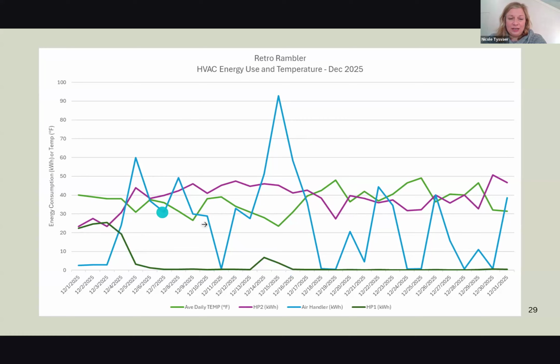And while the temperature dips down, this blue line is the indoor air handler, and it's going kind of crazy. Then in the meantime, it stops listening to the thermostat altogether, so we had days when the system wasn't working at all, and we couldn't quite figure that out.